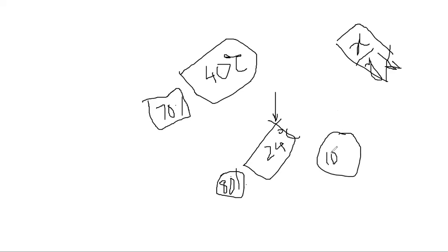Because this relative humidity value keeps on increasing, at one point it will become 100%. Once it becomes 100% and you go further below in temperature, then what will happen? It will maintain 100%, because it cannot hold more than 100%. But the Y value will be lesser than this quantity. So the difference of quantity will come out from the air in condensed form, because it will get condensed and it will come out.